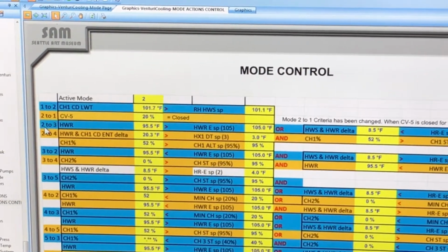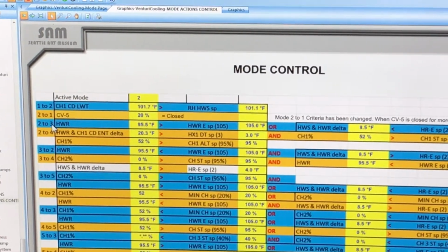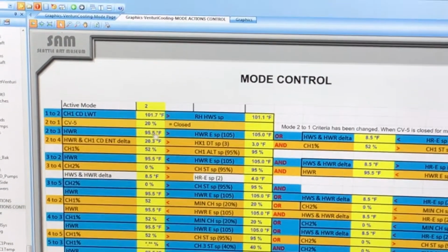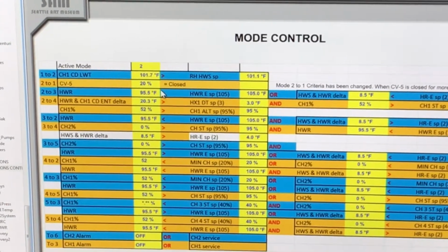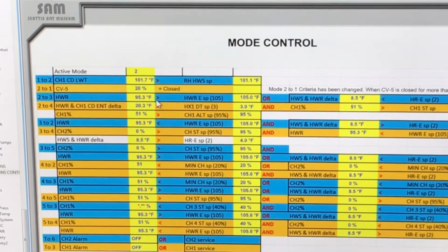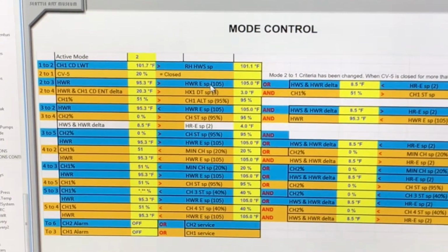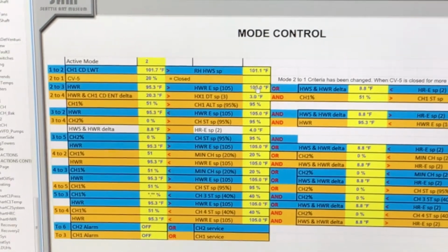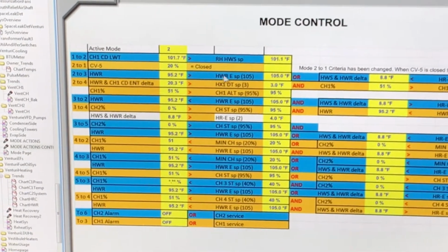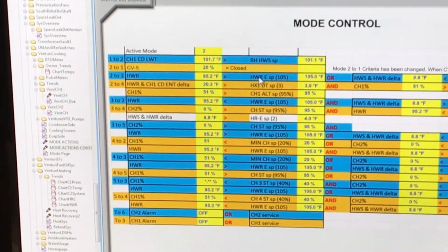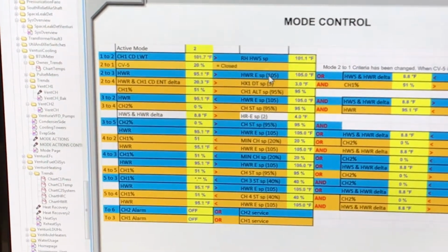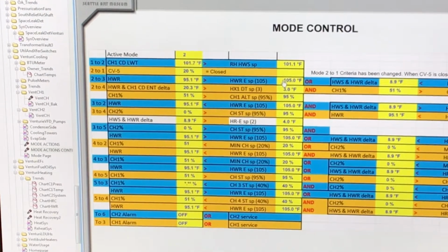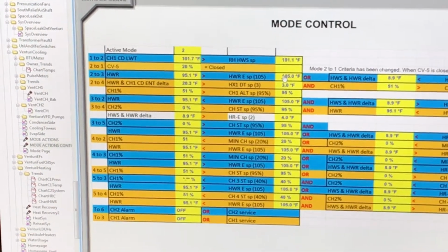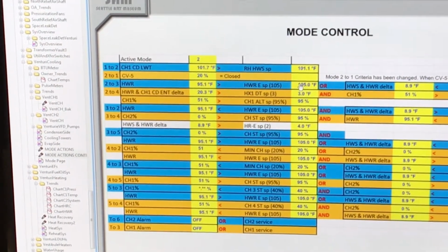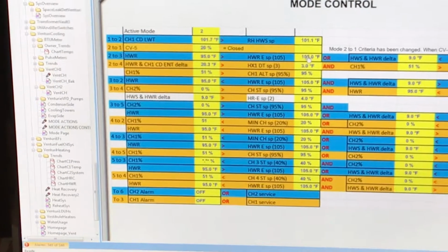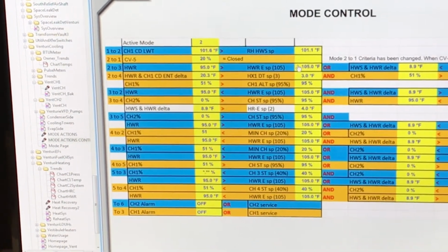So in order to move from mode 2 to 3, the hot water return, whose actual value is 95.5, has to be greater than, you see the greater than symbol, the hot water return set point, which defaults to 105, but that can be changed right here. Right now it's not greater than this set point. Now, if I were to change this set point to 90, it would go into mode 3. So this is one action that makes it go into different modes.